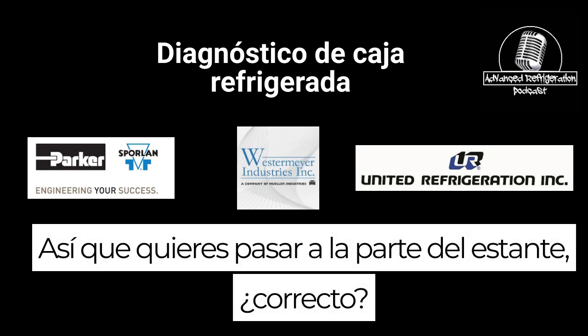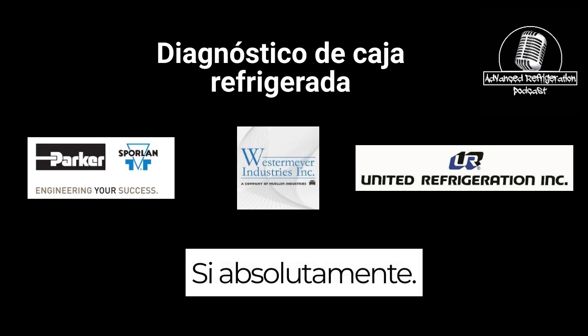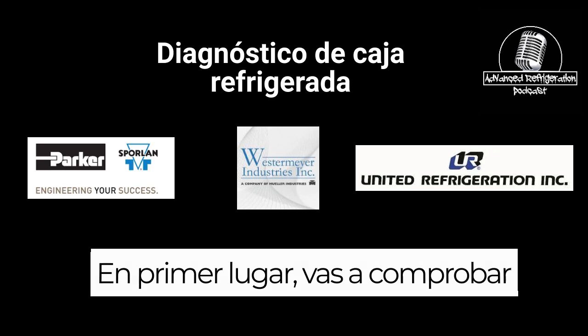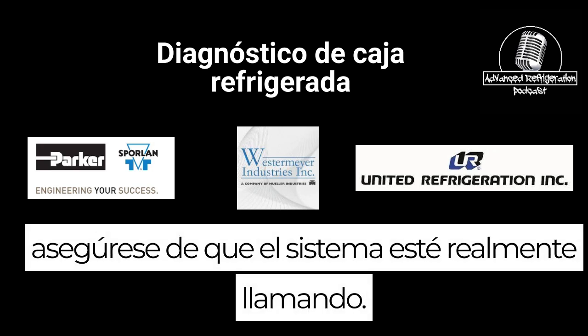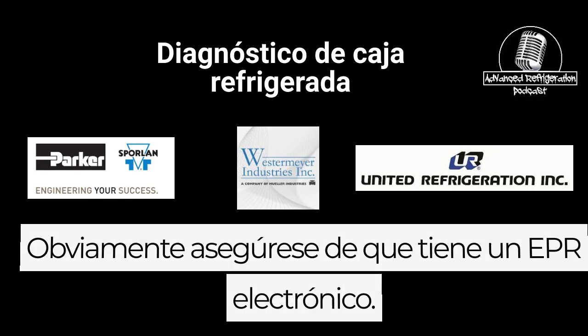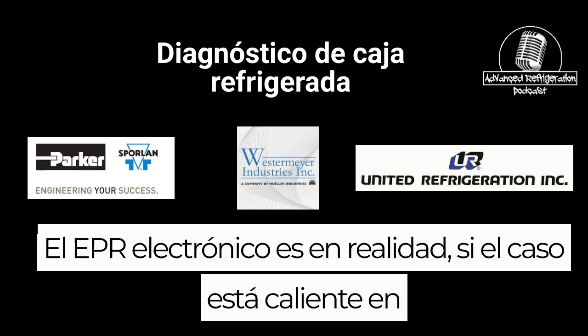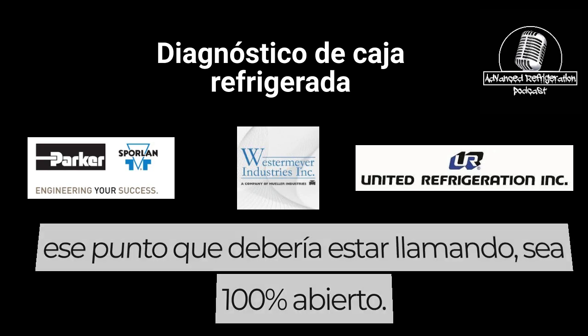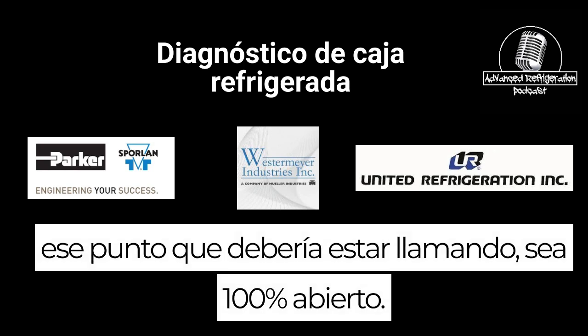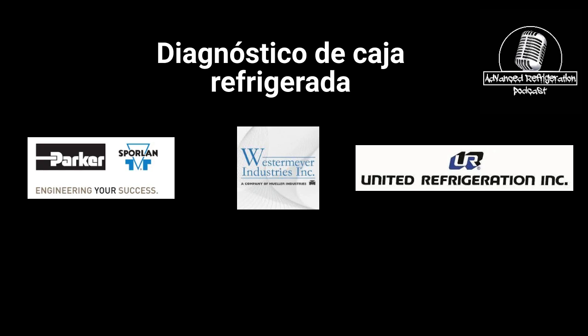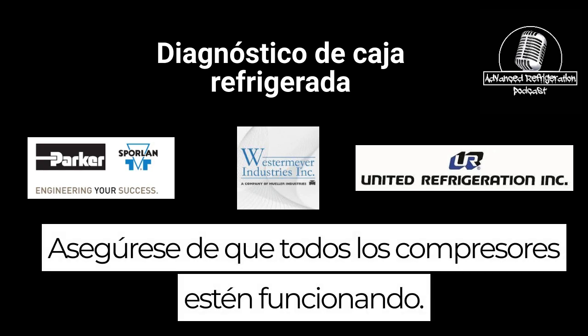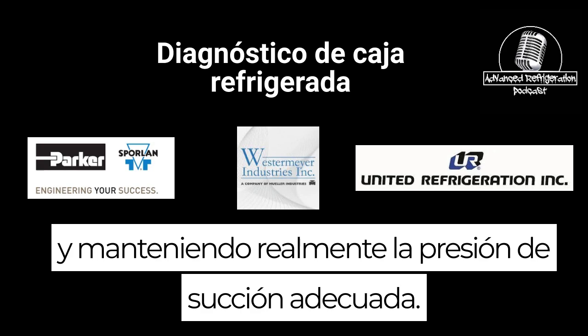So you want to move on to the rack part of it, Brett? Yeah, absolutely. First off, you're going to check to make sure that the system is actually calling. Obviously, if it has an electronic EPR, and the case is warm at that point, it should be calling for the EPR to be 100% open. Make sure all the compressors are running and actually maintaining proper suction pressure.